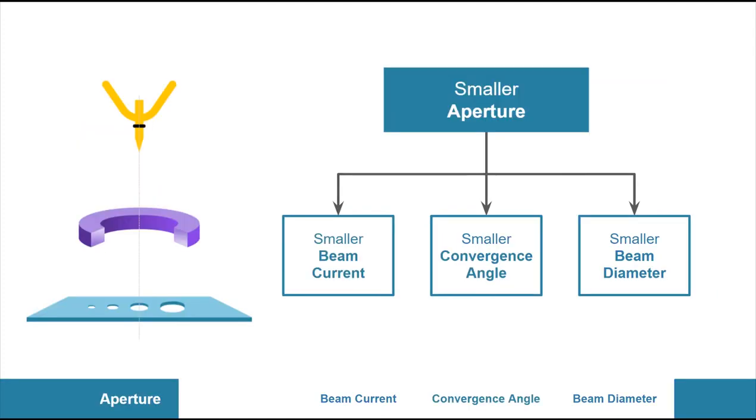The next element in the SEM is the aperture plate. This behaves as you would expect. A smaller aperture will result in a smaller beam current, a smaller convergence angle, and a smaller beam diameter.